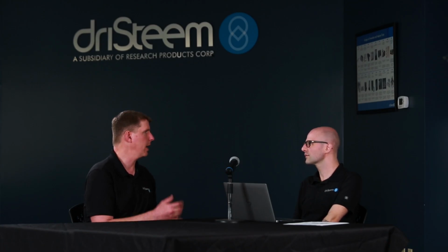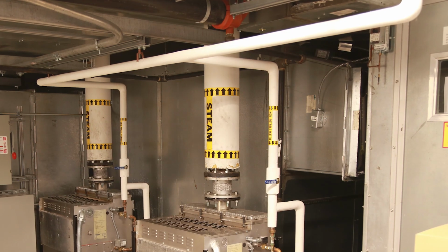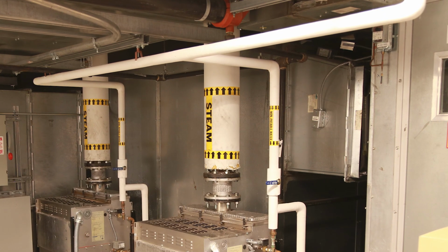When you get into higher capacity systems, your pipe just gets bigger and bigger, and whether that's a threaded connection or you end up getting into flanges to bolt different sections together, the application will determine what it is. Going back to the efficiencies, you want to keep it as steam as possible. Oversizing the piping just creates more opportunity for losses. So insulating it is an important piece, and thinking through how am I going to pitch this? How's the condensate going to get out of the system? Those are some of the other things to keep in mind when thinking of piping, besides the materials.